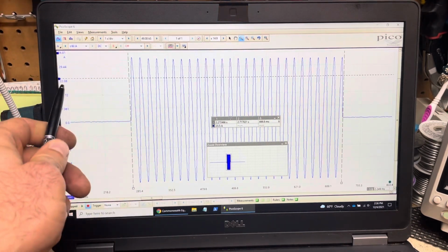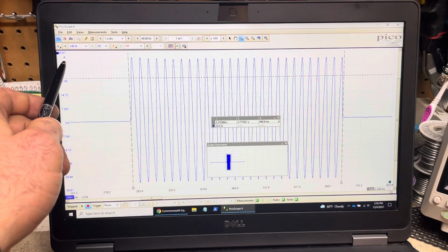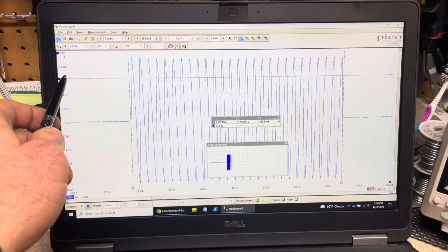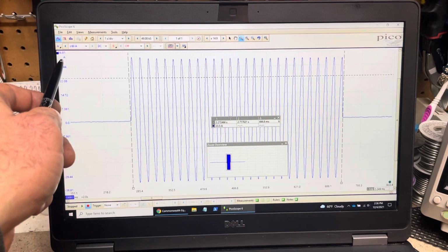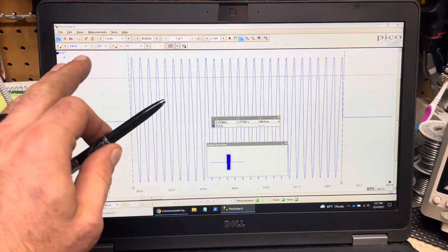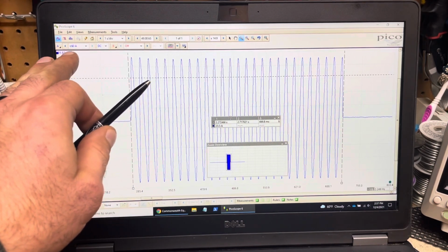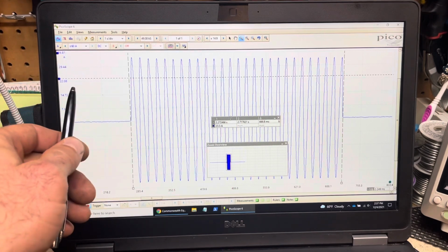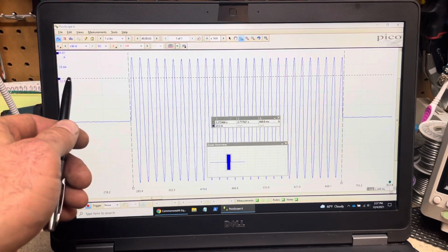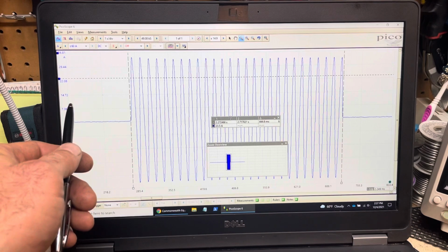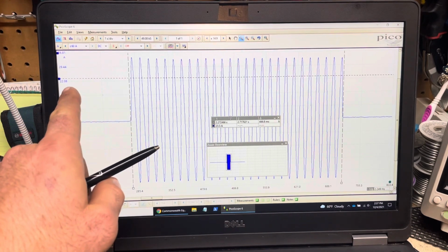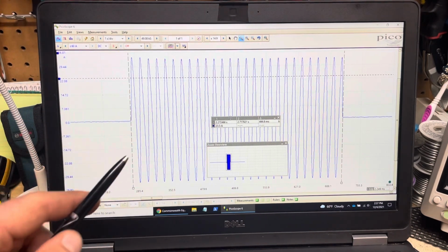I set my amp clamp up to the 60 amp mode so we can capture a lot higher amperage. One thing I want to point out is that even though the clamp is putting out volts, what you're seeing on the screen is amps. I've written a mathematical formula into the probe section that will take that voltage and convert it to the corresponding amperage. So what you're seeing on the screen is actually amps.